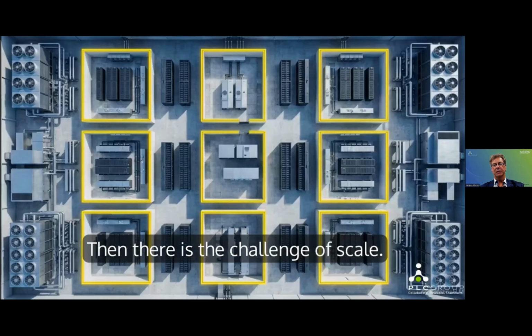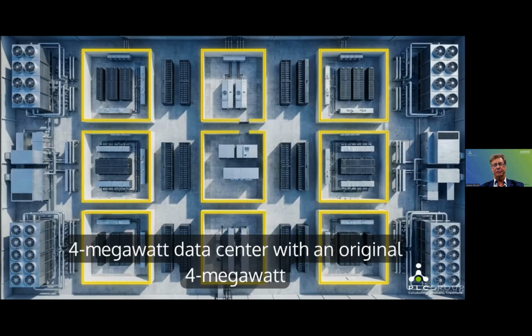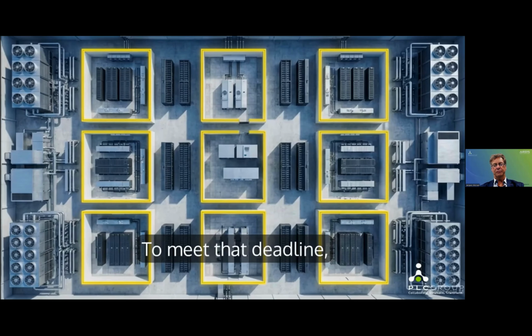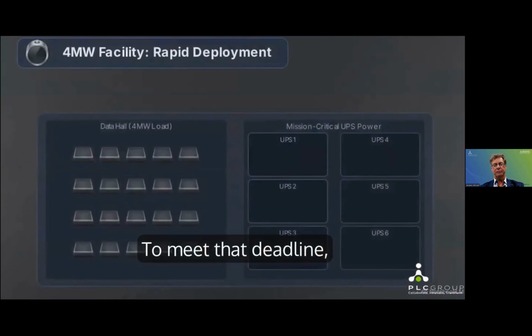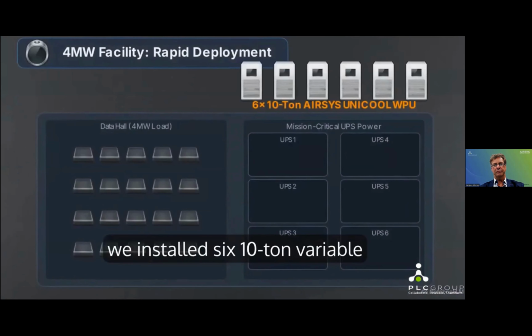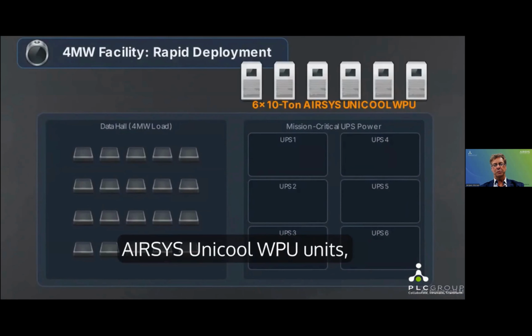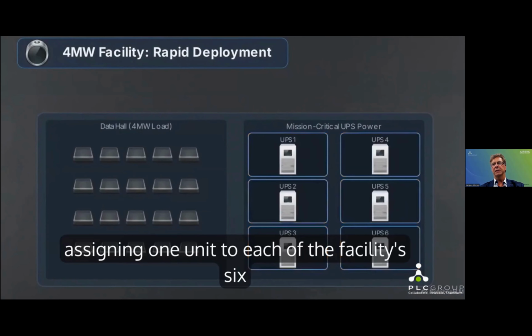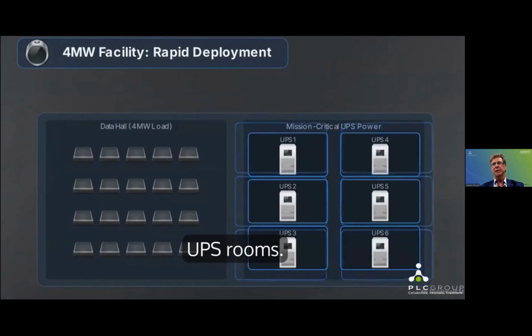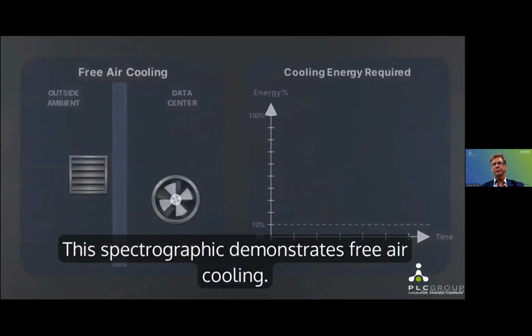Then there is the challenge of scale. We were tasked with fully outfitting a 4-megawatt data center within a rigid 4-month deployment window. To meet that deadline, we installed 6 10-ton variable AirSys Unicool WPU units, assigning 1 unit to each of the facility's 6 UPS rooms. This vector graphic demonstrates free air cooling.